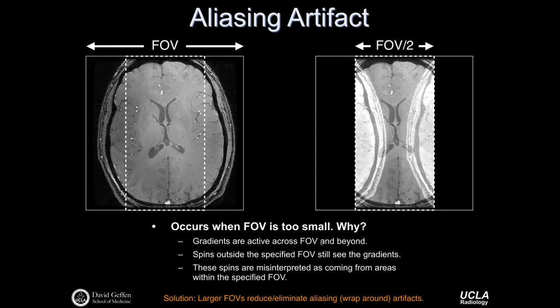The simple solution is to use a large field of view to reduce or eliminate the aliasing or wraparound artifact. However, increasing the field of view will cost some imaging time if you want to maintain spatial resolution. As always, there are trade-offs in MR.